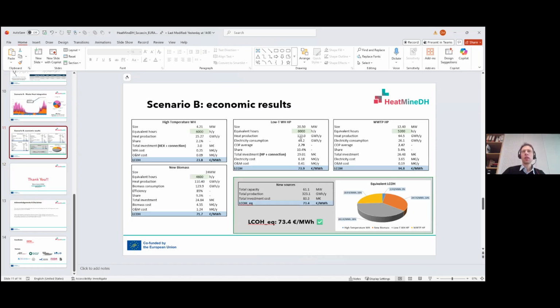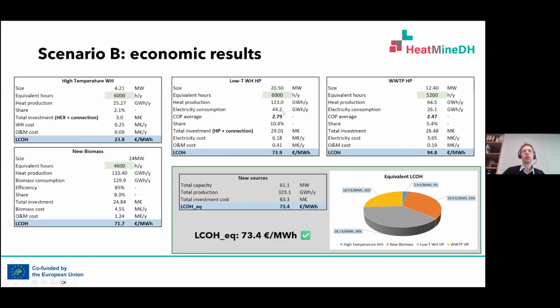You can see here a couple of estimates of COP. Maybe I switch again to presentation mode. You still see my presentation, yes. Right? You see, for example, that for the case of wastewater treatment plants, we estimated an average COP of slightly less than 2.5. Again, assuming the heat pump needs to provide the supply temperature for the network up to 100 degrees. For low temperature waste heat, this is better, of course. The source we assume to be around 25-30 degrees along the entire year.